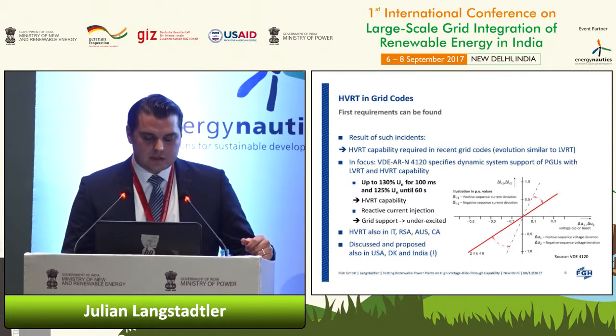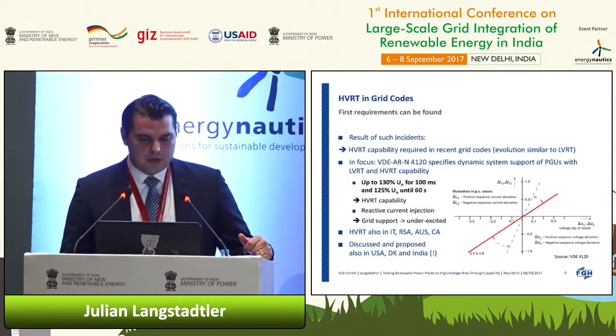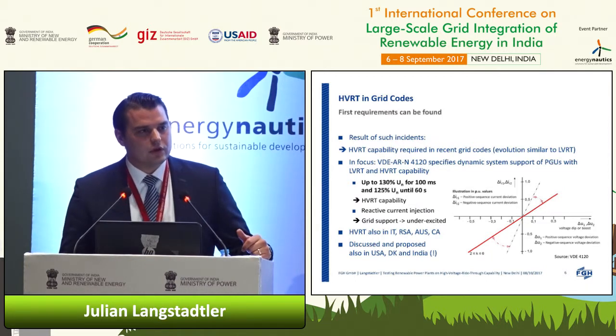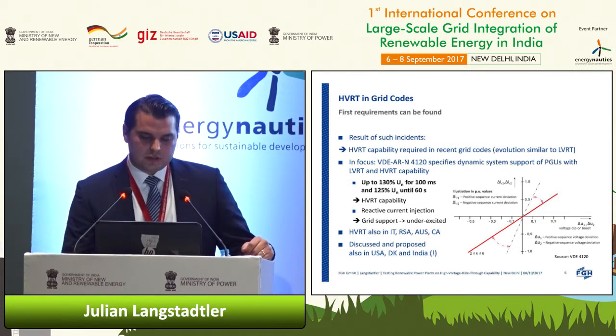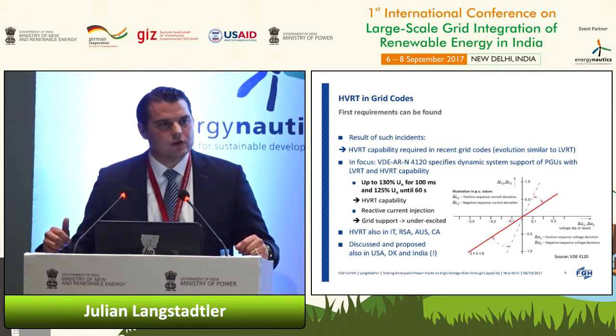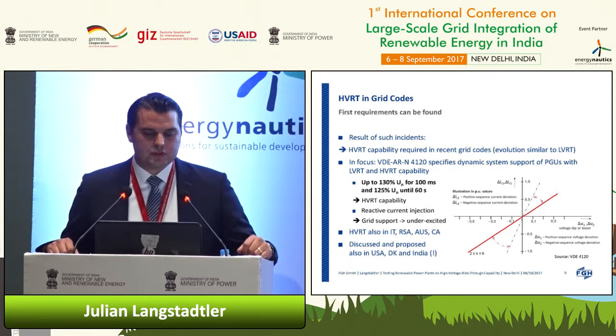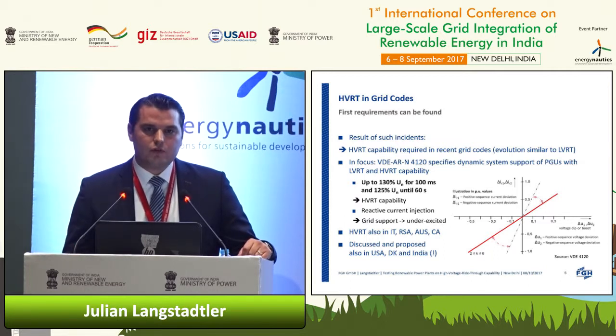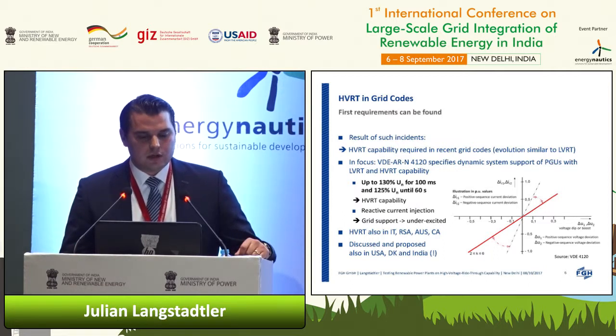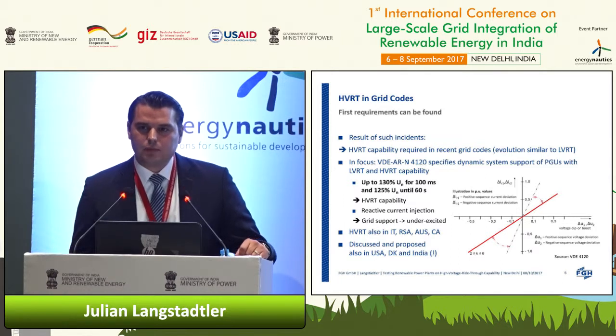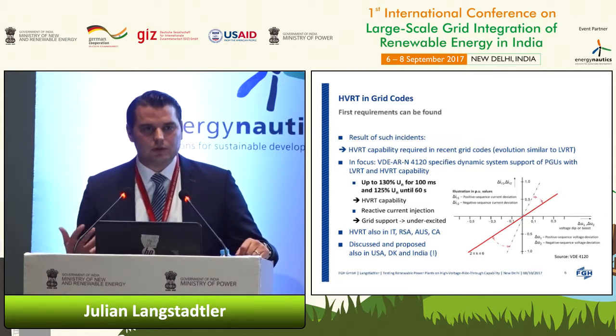And in this regard, I would like to highlight also the German requirement from the new revision of the high voltage grid code that was introduced in 2015 in Germany, where we have an LVRT and an HVRT requirement. And the HVRT requirement says that you have to withstand voltage swells up to 130% of nominal voltage for a period of 100 milliseconds, and in addition, also 125% of nominal voltage until 60 seconds. So this is basically the HVRT capability, so that means that you are able to fault ride through.